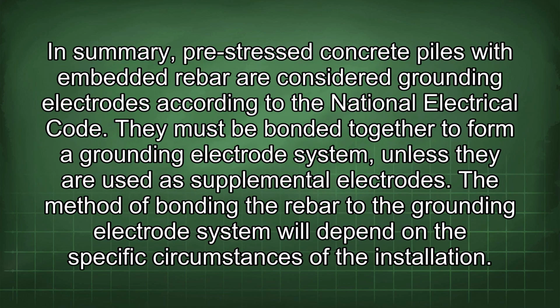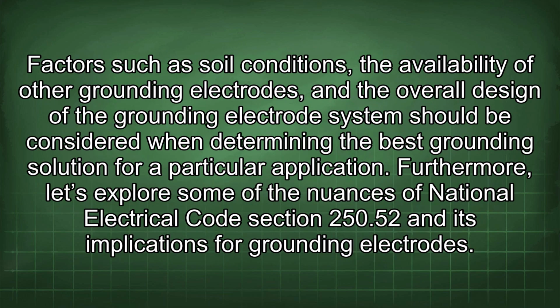In summary, pre-stressed concrete piles with embedded rebar are considered grounding electrodes according to the National Electrical Code. They must be bonded together to form a grounding electrode system unless they are used as supplemental electrodes. The method of bonding the rebar to the grounding electrode system will depend on the specific circumstances of the installation. Factors such as soil conditions, the availability of other grounding electrodes, and the overall design of the grounding electrode system should be considered when determining the best grounding solution for a particular application.